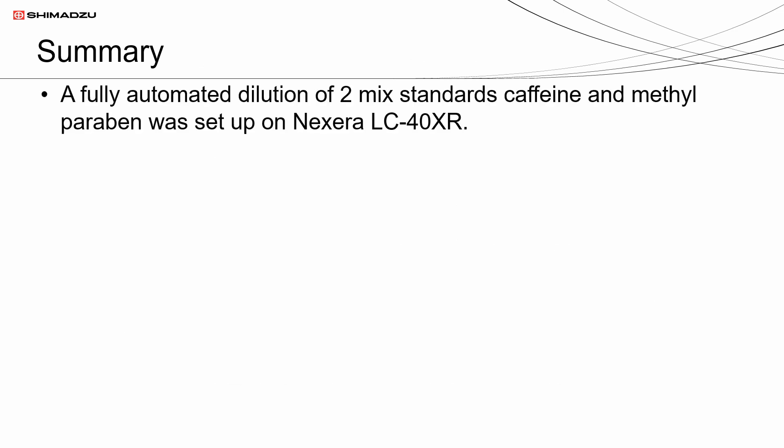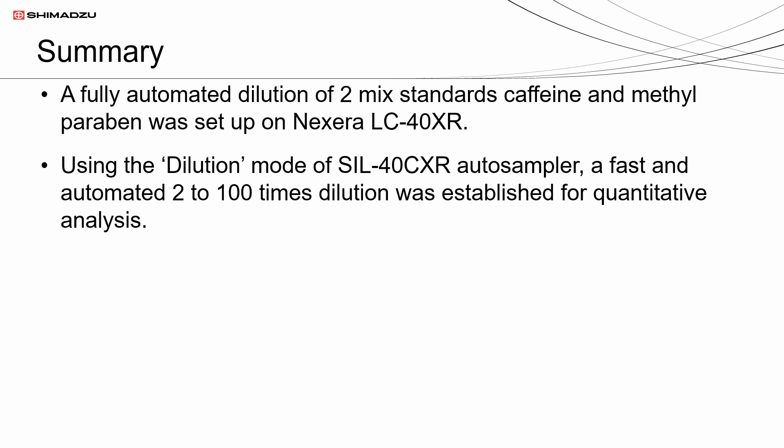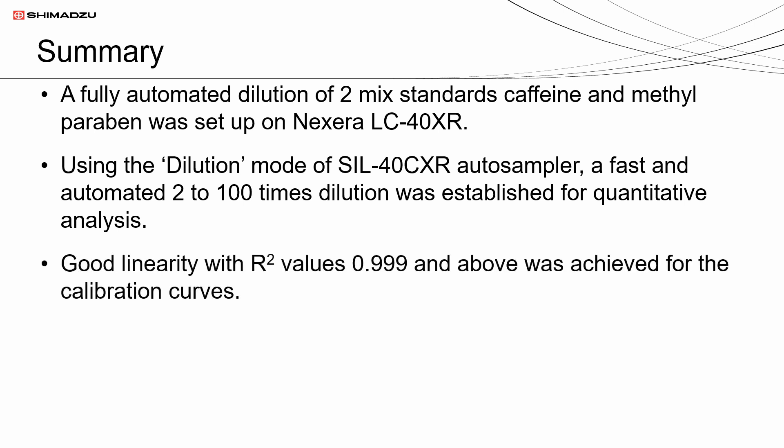We are coming to the end of this video. In summary, a fully automated dilution of two mixed standards, caffeine and methylparaben, was set up on Nexera LC-40XR using the dilution mode of SIL-40CXR autosampler. A fast and automated 2 to 100 times dilution was established for quantitative analysis.